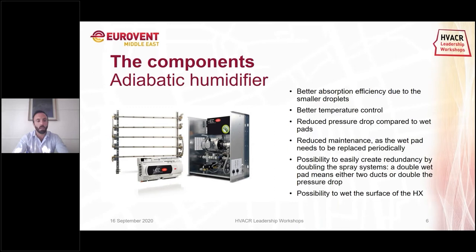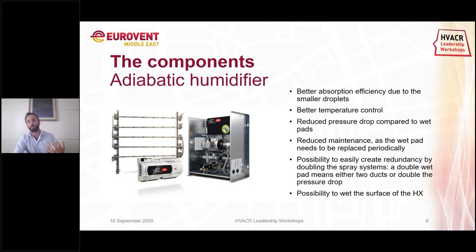The wet pad needs to be substituted, whereas the spray system is just a rack with a cabinet able to pressurize the water. The main characteristic of the adiabatic humidifier at medium pressure compared to the wet pad is that it is able to wet the heat exchanger — not only cooling the air before the heat exchanger but also inside it. From our experience and tests in our lab and university, it is really important to wet also the surface of the heat exchanger.